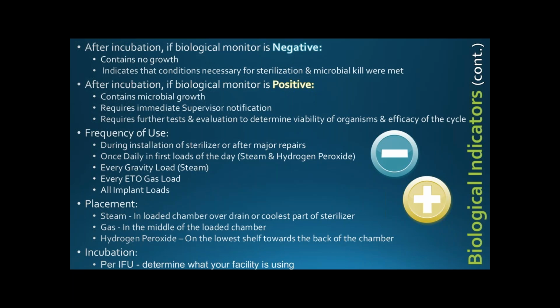You need to make sure of the incubation time for your BI. There's a 3-hour BI, there's a 24-hour BI. So the biggest reason why you want the biological indicator with the shorter incubation time, especially the 1 hour with steam, is that by the time you're able to read out your biological indicator, because it's incubated for that hour, your instruments are cool enough to touch and release. So if it's 24 hours, then that instrument has already cooled, been released, right? And it's put on a shelf.